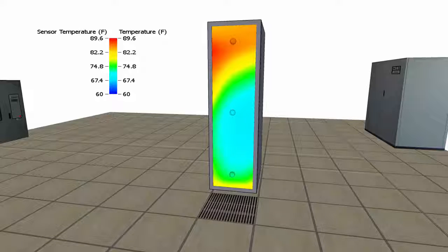Even after following suggested placement guidelines, it appears that the temperature sensors do not provide an accurate picture of the cabinet inflow temperature profile. From this image alone, we see that small hotspots can exist near sensor locations, but can go undetected. And with just 3 data points, thermal mapping would be unable to capture the curved temperature gradient between the sensor locations. This is an issue that was explained in part 1 of the series.